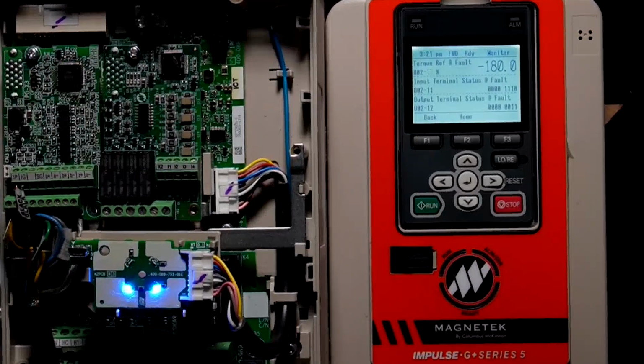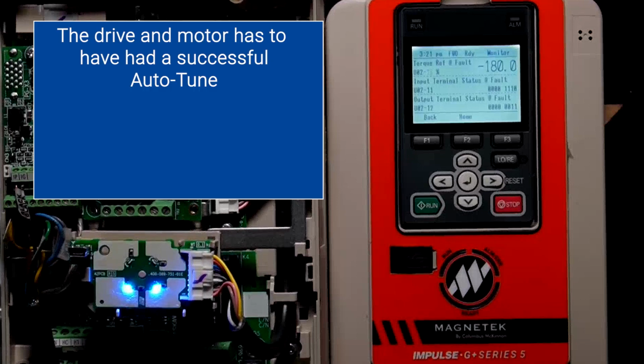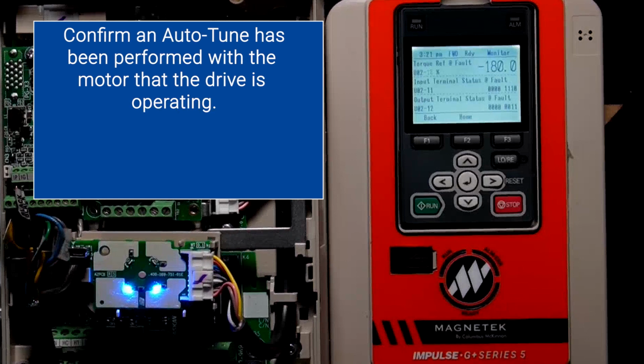Now, one more issue with being at the torque limit and generating a DEV fault. If the motor and drive have not been auto-tuned, that needs to be confirmed or done first. The drive, if it's not been auto-tuned with the respective motor, does not know what output current relates to what motor torque. So confirm that an auto-tune was done.